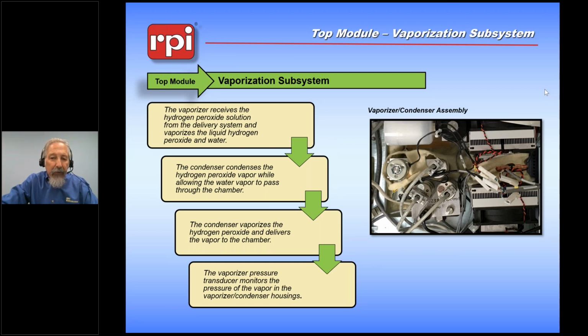there is a tray in the bottom, approximately under here. It has an opening in it. It's heated up to a very high temperature. As soon as the peroxide comes in through that piece of tubing we talked about earlier, it's immediately vaporized along with the water it contains, leaving behind any salts or preservatives that are used in the assembly of the cartridge.